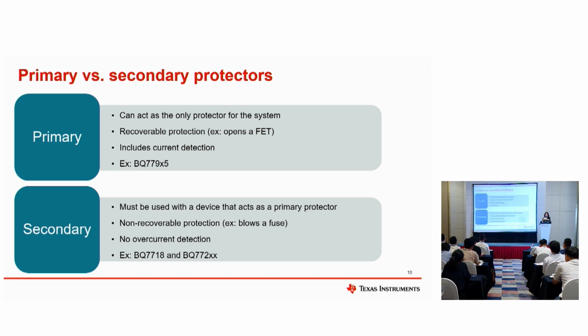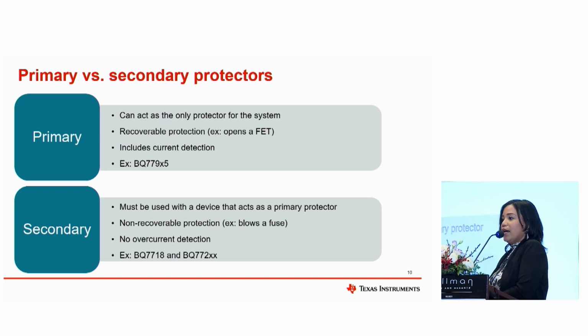When we talk about primary versus secondary protectors, we're looking at a recoverable failure versus a permanent failure. With primary protection, we can have a fault like an overvoltage, we open the FET, and the moment the fault goes away, we reconnect the system and continue operating. With secondary protection, we're looking at a permanent fail mode. If your primary protection fails, you need to make sure the safety of your system is guaranteed. Some safety standards will require you to have a permanent fail or secondary protector on your system. Typically, secondary protection will blow a fuse in your system, so at that point the battery pack will be scrapped. Having that redundancy means that if it's a temporary fail mode, you can protect your battery, and the moment the failure is permanent, you make sure no further damage happens.